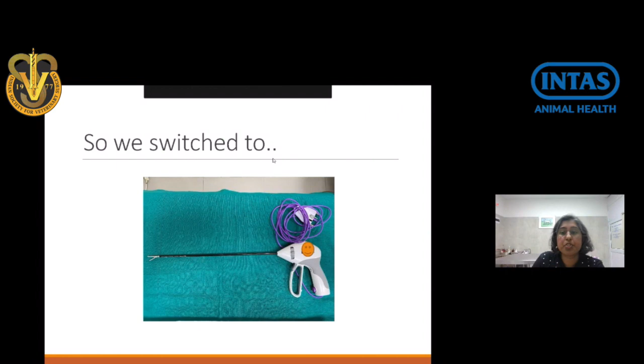So keeping this in mind, what we decided was to switch. So we switched to a laparoscopic vessel sealer and cutter. A laparoscopic vessel sealer and cutter is basically a specialized bipolar device that combines pressure and the bipolar energy from a specialized generator. It forms an effective seal by fusing collagen. After you fuse collagen on the same site, you can choose to cut simultaneously after sealing. This also gives an effective seal up to 7 millimeters in diameter.